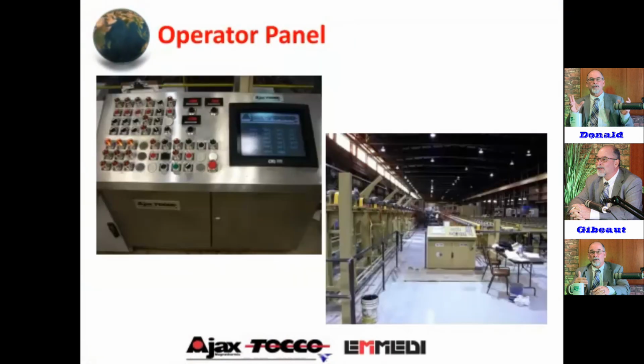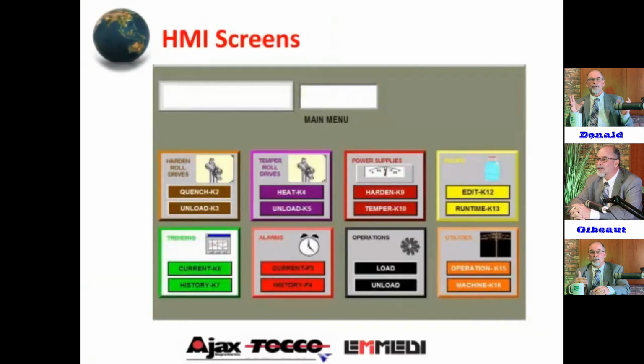Going into the controls, I've run enough of these lines over the years that we like to, in our engineering department, it's not old school, it's just what I say is sound engineering. A lot of people have gone to HMI and PLCs only. And in the startup phase, and especially when you're troubleshooting and you're trying to work with a line progressively, these manual controls on the left, added to the HMI screen and PLC controls, really give you flexibility in running the line and maintaining it.